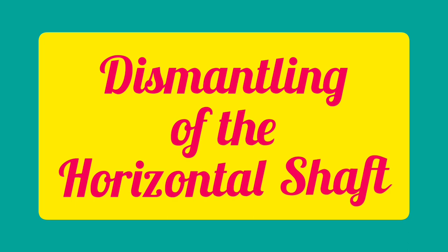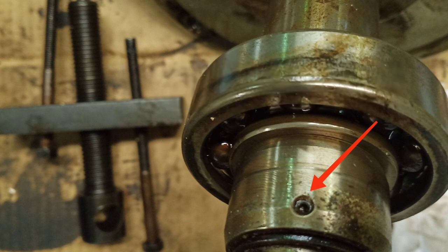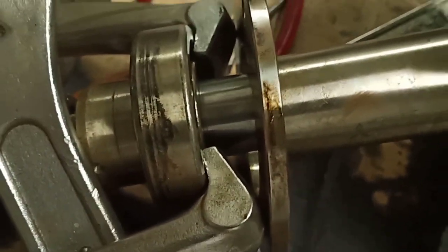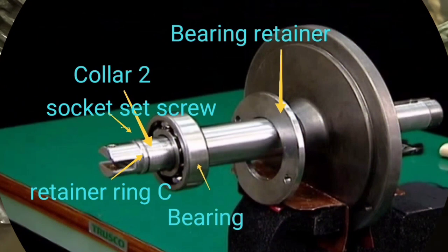Dismantling of the horizontal shaft. Remove the retainer ring C. Loosen the socket set screw securing Collar 2. Remove the pump side bearing together with the Collar 2 using jack bolts, push bolts, and handle or a puller. Then remove also the bearing retainer.